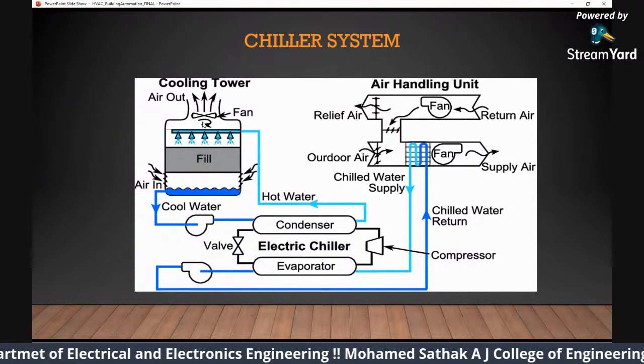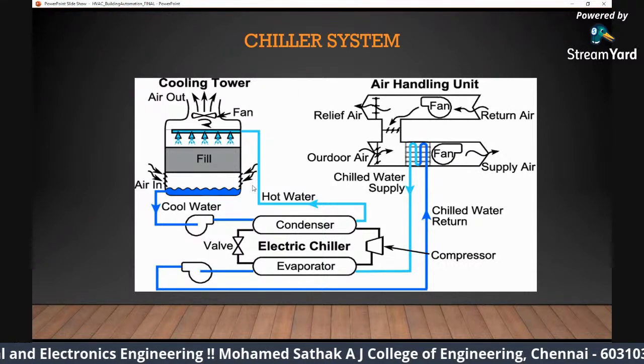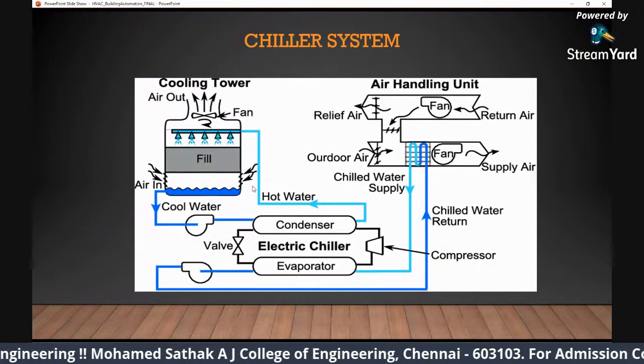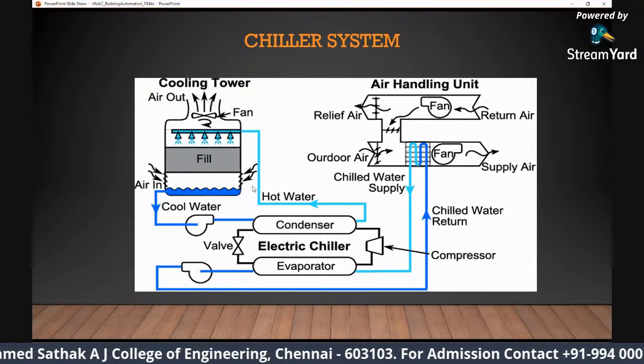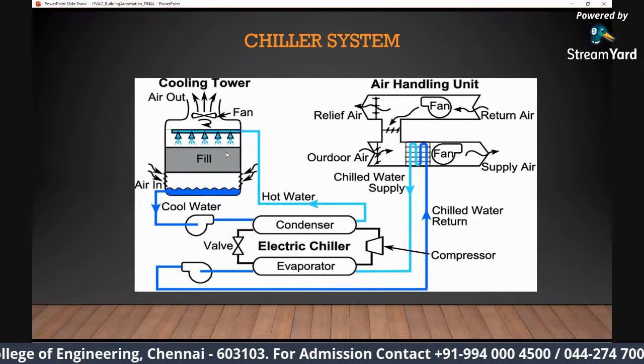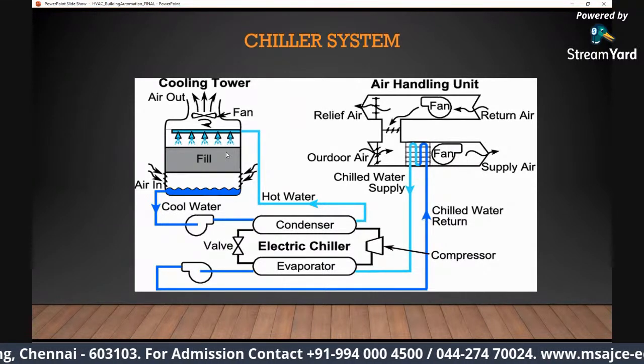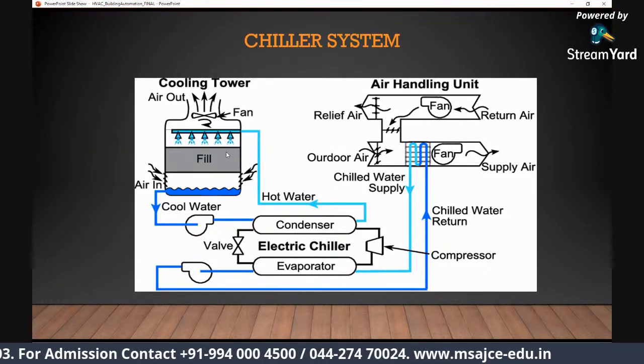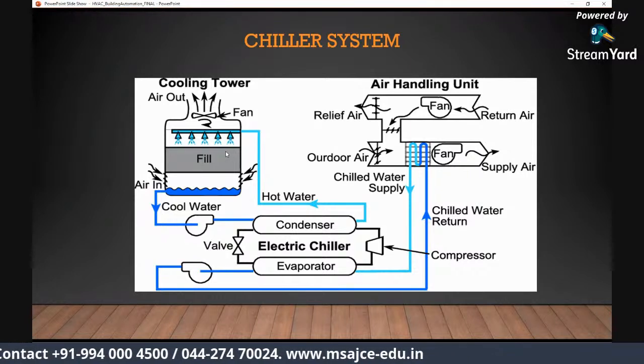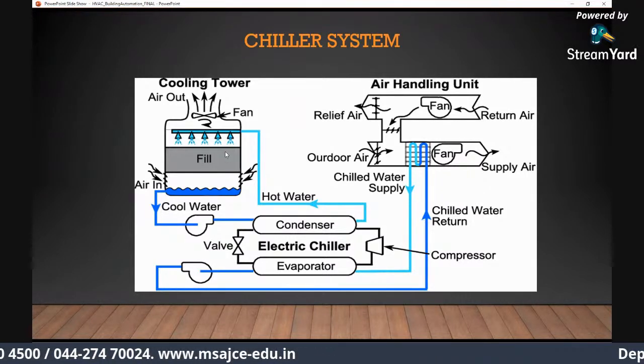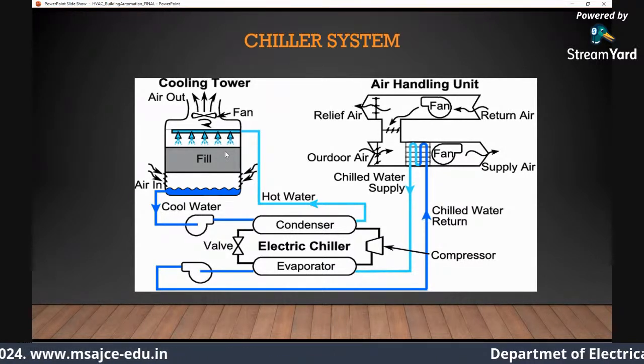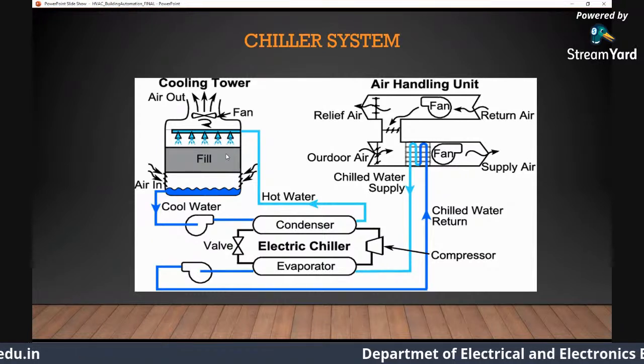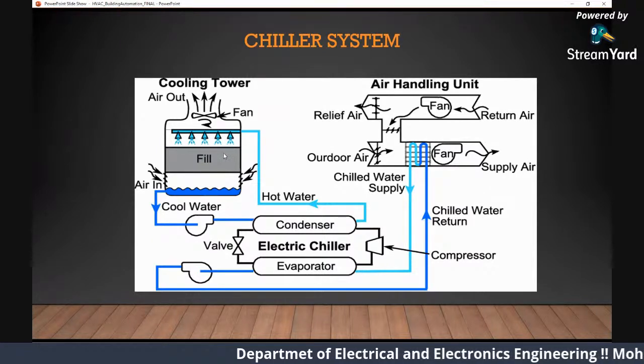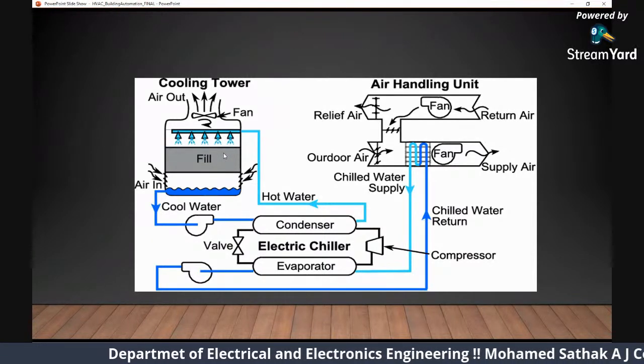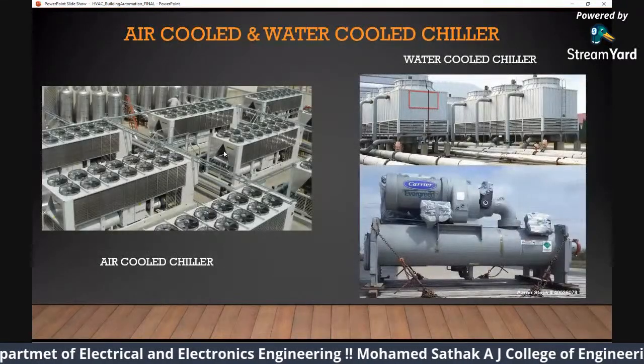Again, if you see the cooling tower, if it had been an air cooled chiller, you'd just have multiple fans above your condenser section. You won't have this cooling tower at all. Since water is being used to cool your refrigerant in your condenser, it's called a water cooled chiller. If it is just fans being used in the condenser to cool your refrigerant, it's called an air cooled chiller. Now just look into this sketch in detail, and if you look into this picture, you'll know.